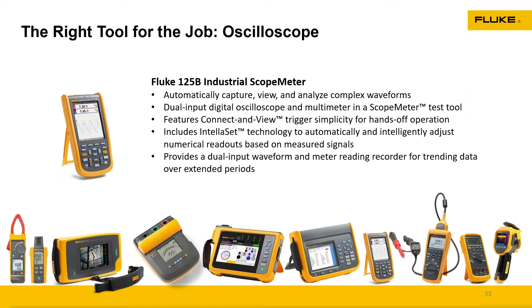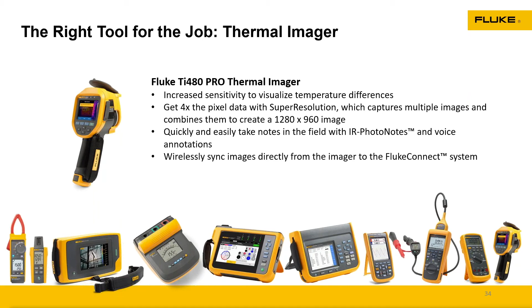One of the keys is thermography. I can't stress enough, thermography is a huge one. Some of these big sites actually have drones now with a thermal imager built onto the drone itself, and they're doing annual or even biannual scans of the system, and then taking that and putting it into their reports to see if any failures are happening or what's going on. But even a handheld device is going to allow you to walk through that system and see if you have any hot spots, see if any of your bypass diodes are blown on the panels themselves. You could see hot spots in your combiner box as well as in your inverter, and be able to do some troubleshooting and analysis with your thermal imager.